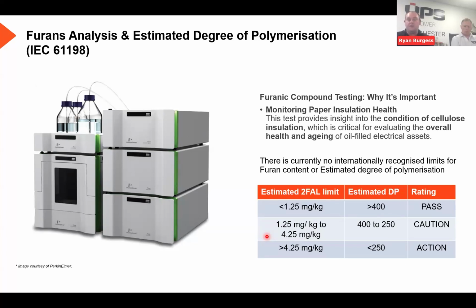So there are two ways you can determine the strength of that paper. You can either do a physical DP analysis, which would require de-energizing the asset, draining the asset, taking several cuttings from the windings themselves, and then sending them off to a laboratory for physical testing, which is a very expensive task. And as well, when you're taking samples, it's not just one sample you need from that winding, you need to take several samples, as each layer of paper will be degrading differently over time. The best way to do this is through furan analysis and the estimated degree of polymerization. As one, it's significantly cheaper, and two, it doesn't cause damage to the asset. That damage, if it is detected, has already been performed, is already happening internally. You're not adding to that by going in and taking a physical sample.